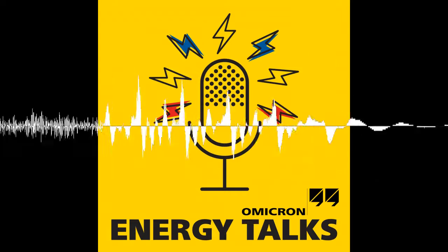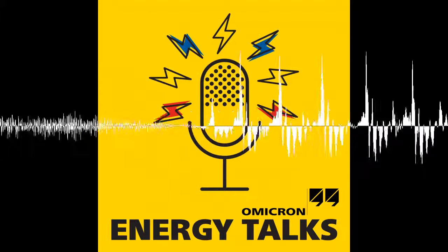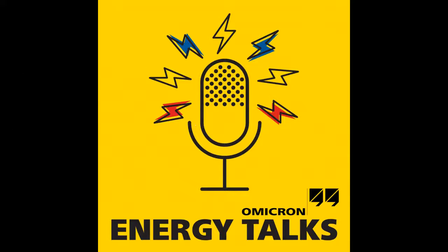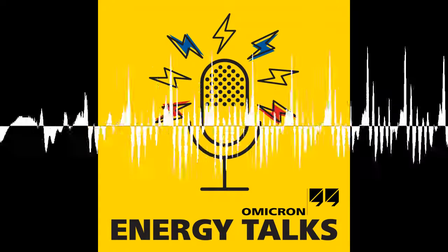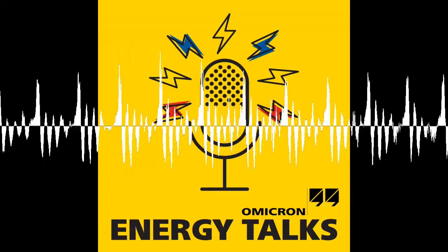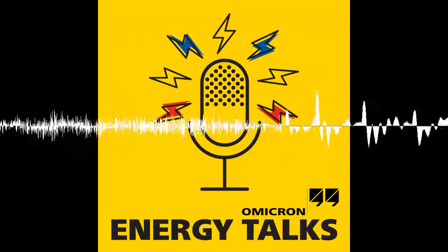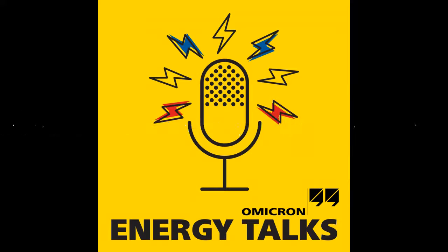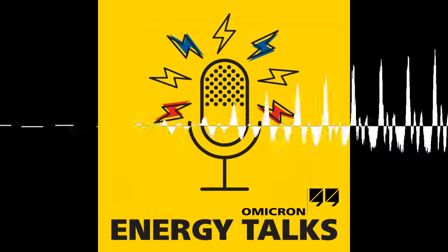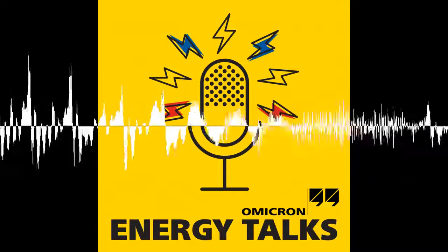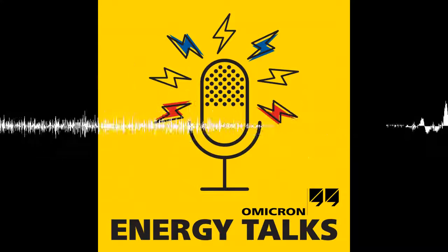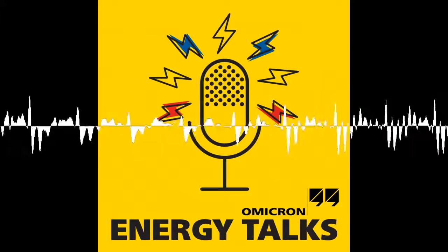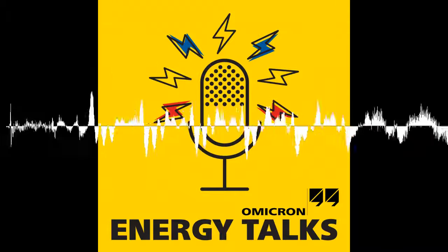In this episode of Energy Talks, my guests are OMICRON voltage transformer testing experts Felix Feustel and Thomas Bischof. They will introduce a new measurement method they developed using OMICRON's VOTANO 100 for determining C divider capacitance on capacitor voltage transformers, or CVTs. Felix and Thomas will describe the significance of this new patented measurement and how it enables capacitive values to be reliably and automatically determined using the VOTANO 100, regardless of the CVT design.